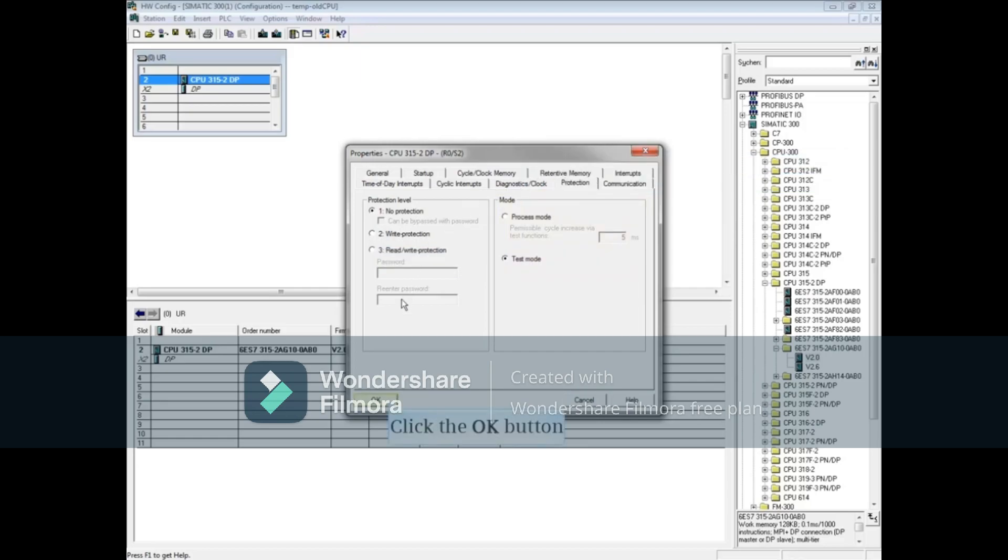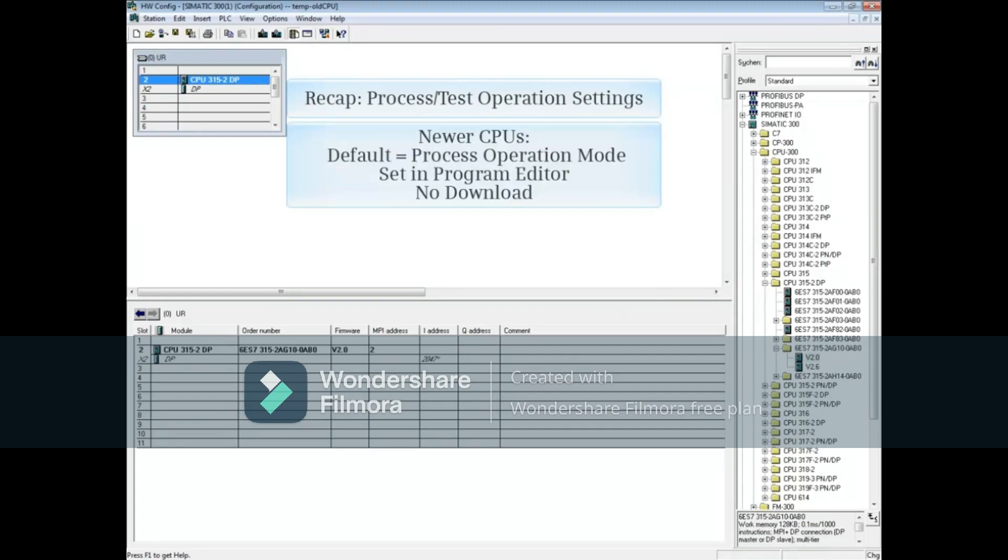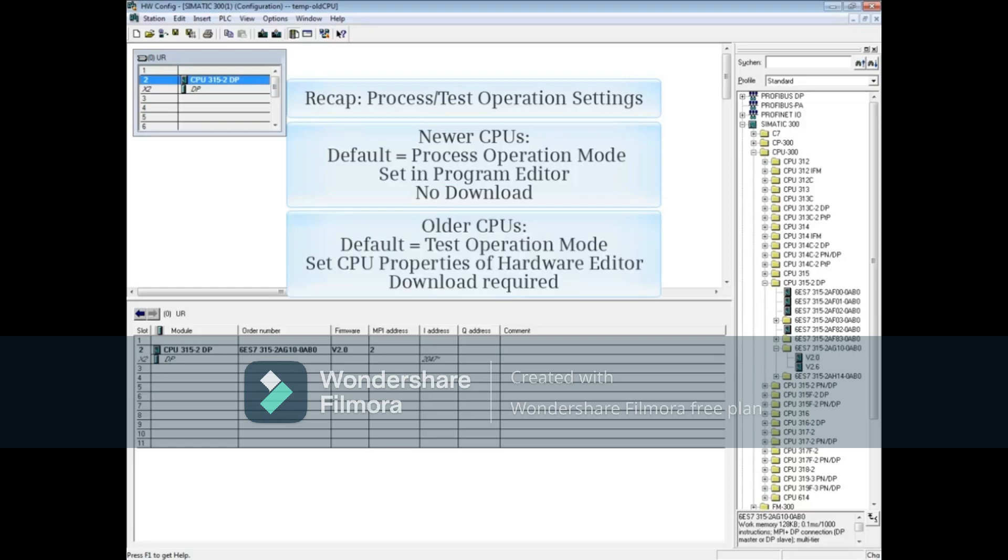You've seen that for newer CPUs, the default is Process mode and changes are made in the programming editor with no download. For older CPUs, the default is Test mode and the selection is made in the CPU's properties of the hardware configuration. A download is then required. That concludes this video.